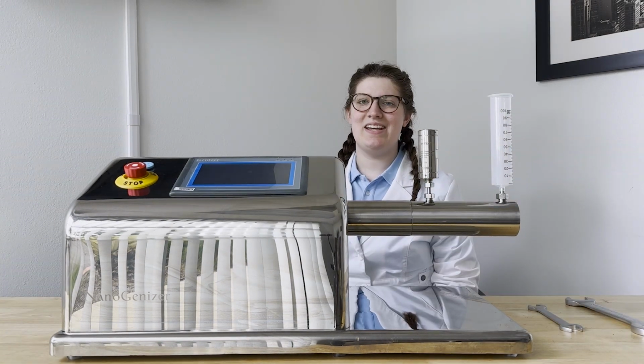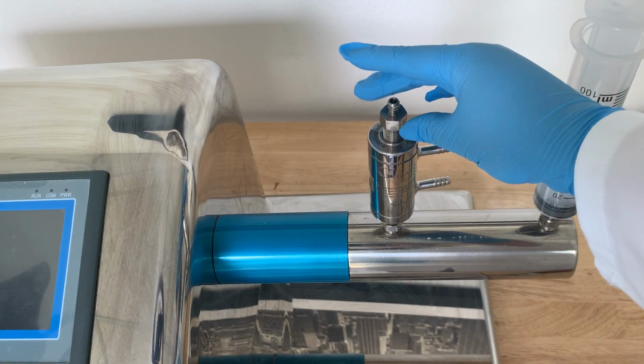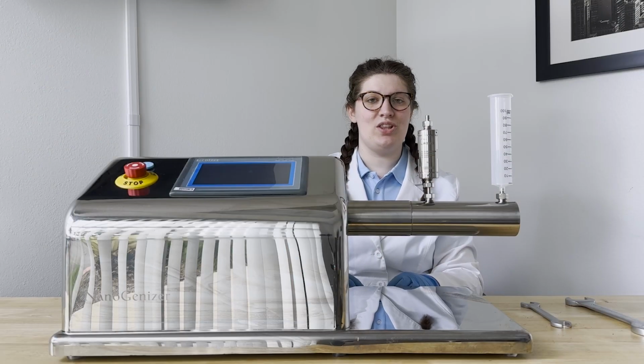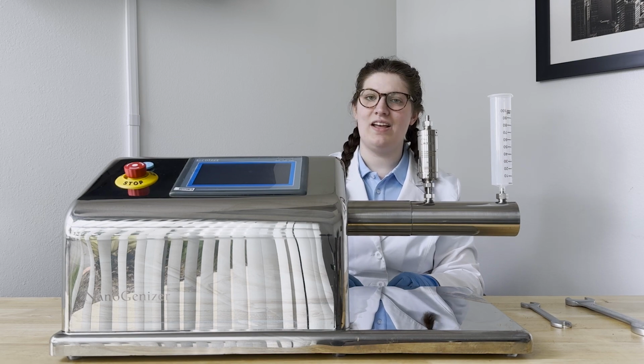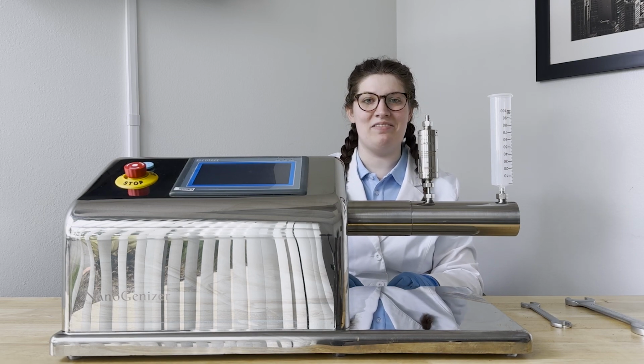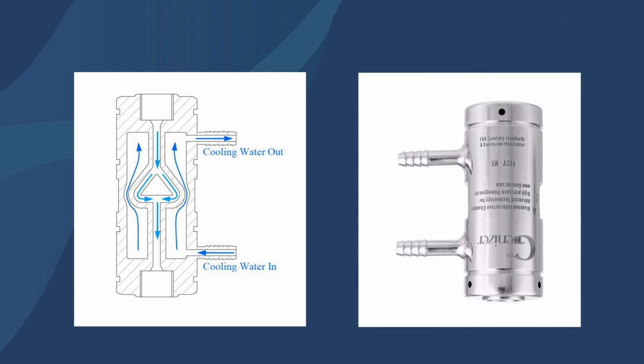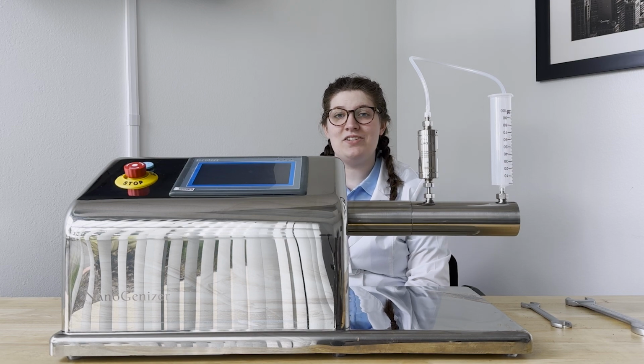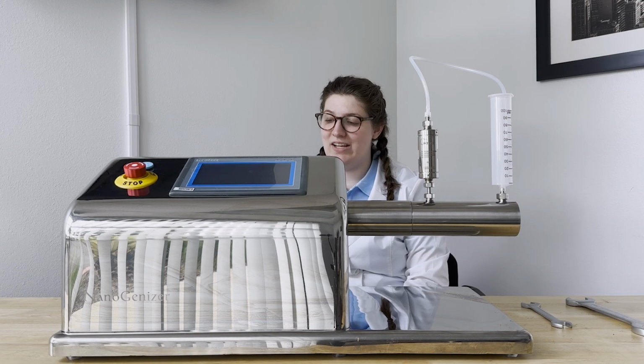If you're not using an additional chamber or heat exchanger, now you can attach your outlet valve. You can attach either a luer lock syringe or tubing to the end of your outlet valve. If you are using real-time heating or cooling for your sample, you can attach the water in and the water out. Before turning on your machine, mind these warnings.